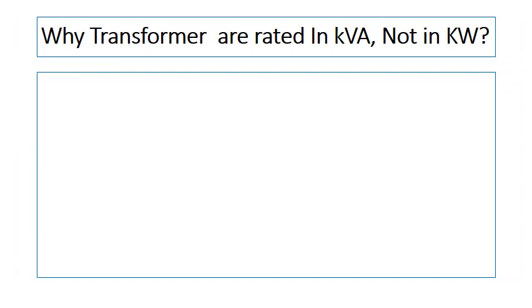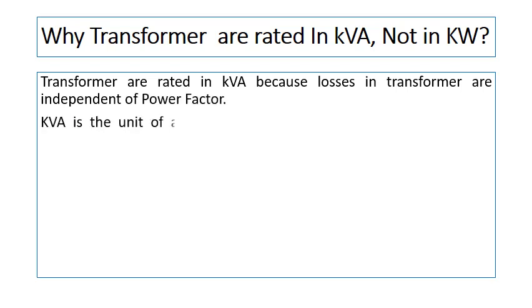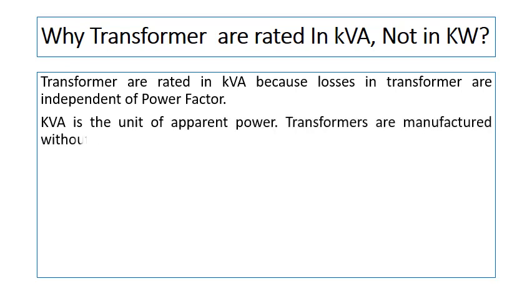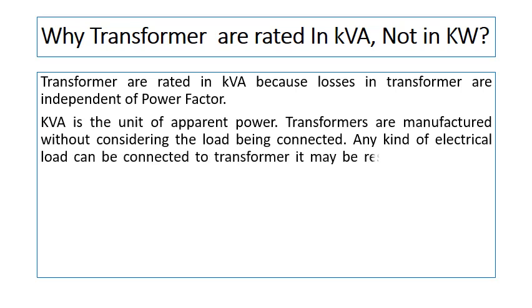Why are transformers rated in kVA, not in kW? Transformers are rated in kVA because the losses in a transformer are independent of power factor. kVA is a unit of apparent power. Transformers are manufactured without considering the load being connected to them. Any kind of electrical load can be connected to a transformer. It may be resistive, capacitive, inductive or a combination of loads.